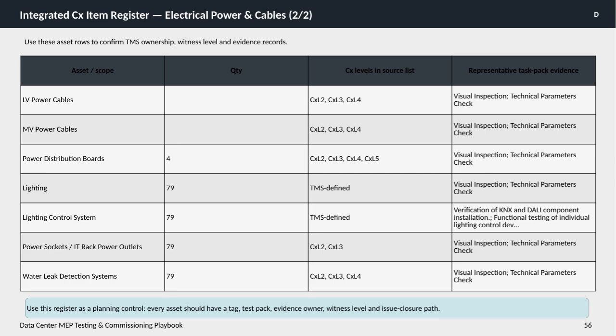For lighting control systems, there's an added layer of verification involving component installation like KNX and DALI, as well as functional testing of individual devices. Importantly, this register isn't just for tracking. It acts as a planning control. Every asset must have a clear tag, an associated test pack, a designated evidence owner, a defined witness level, and a process for closing out any issues. This ensures accountability and thoroughness across the commissioning process, helping us maintain quality and safety standards throughout the project.